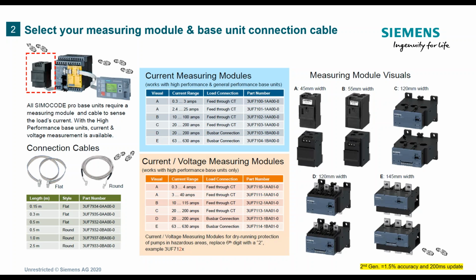Okay, and that's where we come in here with this guy, is that we're able to separate the higher voltage, where you have to address your PPE because you're opening up a 480 panel, and if you kept the 480 on one side and kept the lower voltages, the 24 and the 120, on another, then you can just wear standard PPE. All right, then the accuracy of these CTs, we're at 1.5% at 200 millisecond update rates. Okay.